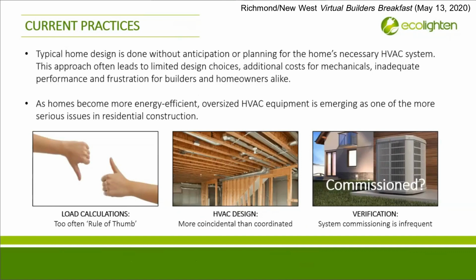The HVAC is either shoehorned into the building as was priced, or it's modified with change order extras after it's too late to do any meaningful coordination. We might get lucky and there's no problems, in other words, coincidence, but more often the system is oversized, costs more than it needed to install, used bigger ducting than was necessary, is going to short cycle, costs more to operate, and not last as long. In addition to all that, it's probably going to be noisier and more uncomfortable than it could have been.